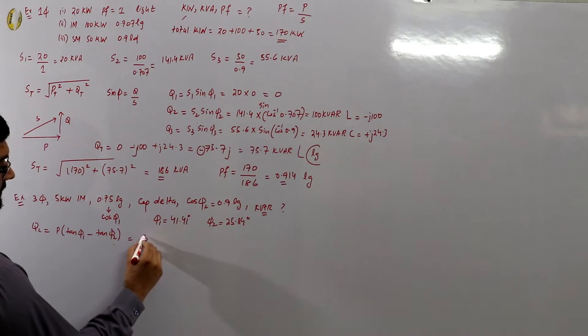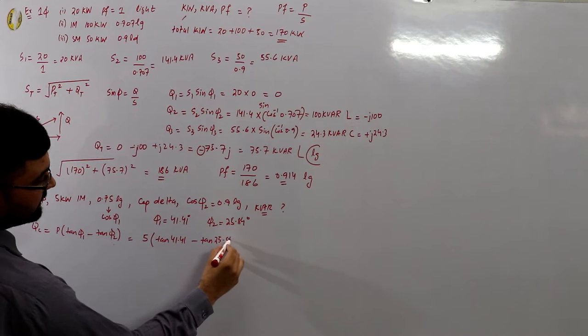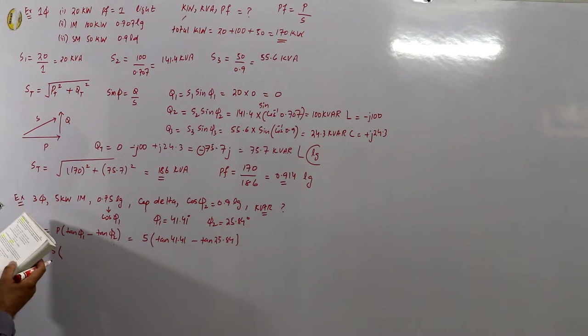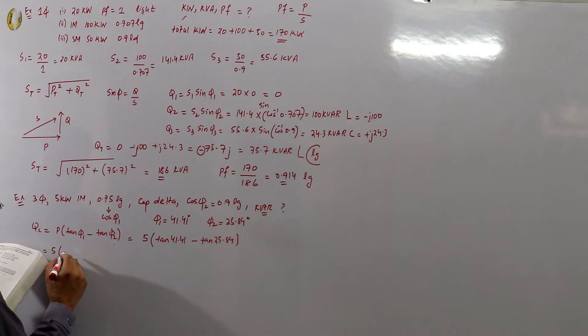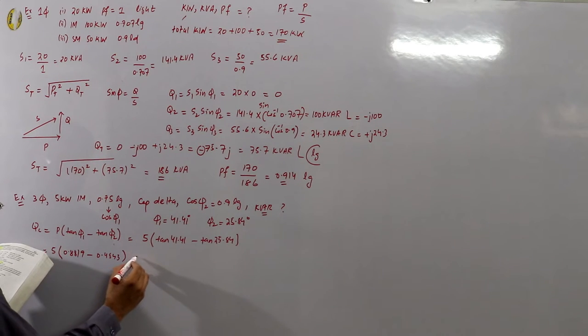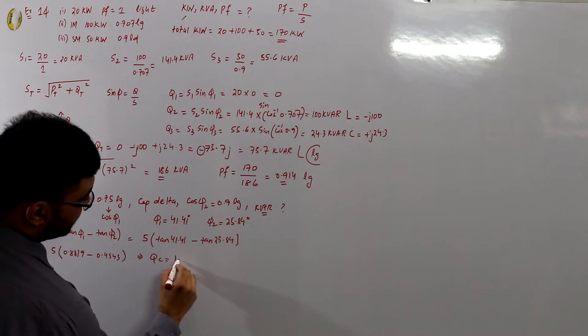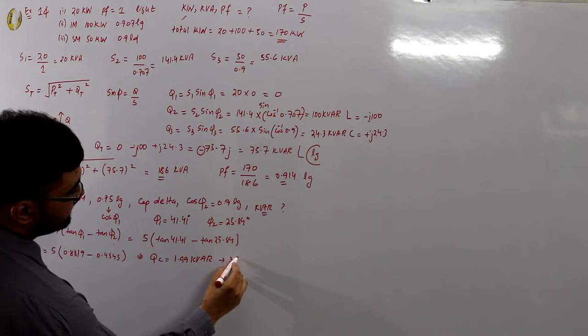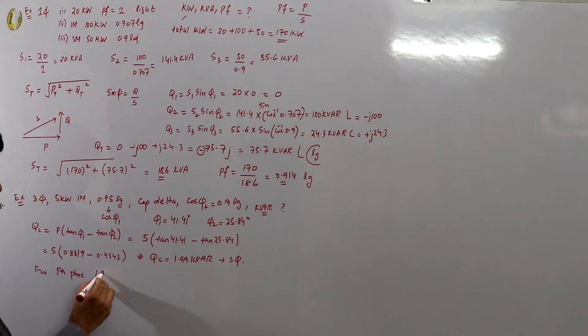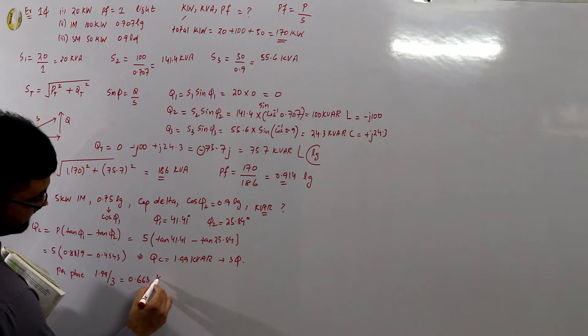Using the formula Qc = P × (tan φ₁ − tan φ₂): Qc = 5 × (tan 41.41° − tan 25.84°) = 5 × (0.8819 − 0.4843) = 1.99 KVAR. Since this is a 3-phase system, the per-phase value is 1.99/3 = 0.663 KVAR per phase.